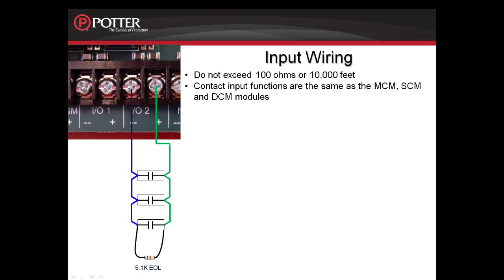When wiring either the I/O circuits on the PSN-1000 smart power supply or an I/O circuit as an input on the fire alarm control panels, those circuits cannot exceed 100 ohms or 10,000 feet. They need an end-of-line resistor of 5.1k ohms. The contact input functions of these circuits are the same as they are for the MCM, SCM, and DCM modules that can be installed on the SLC circuit in the field.